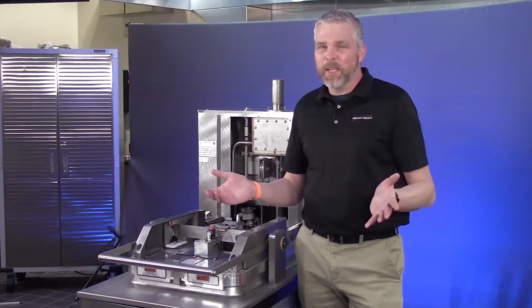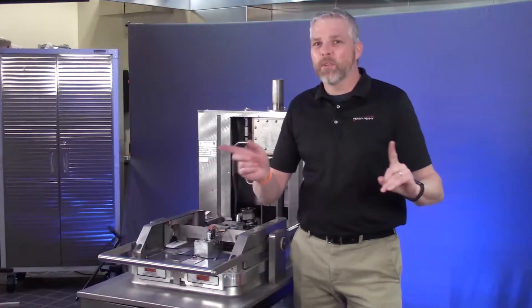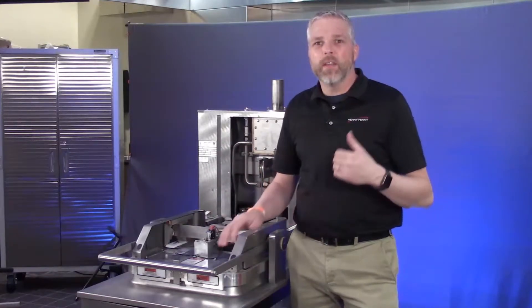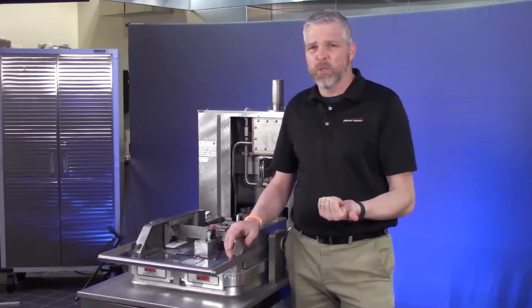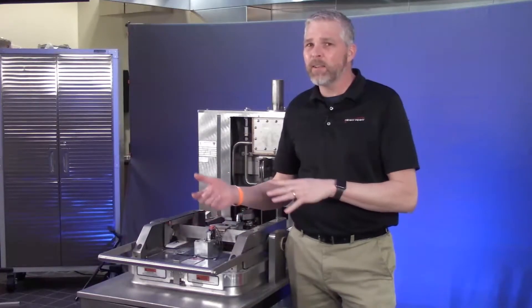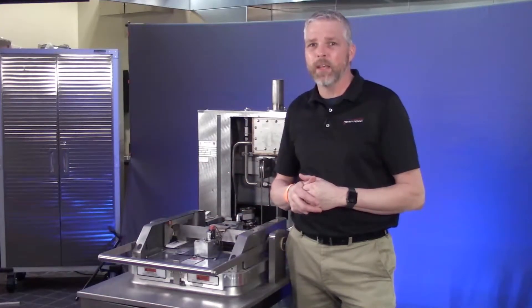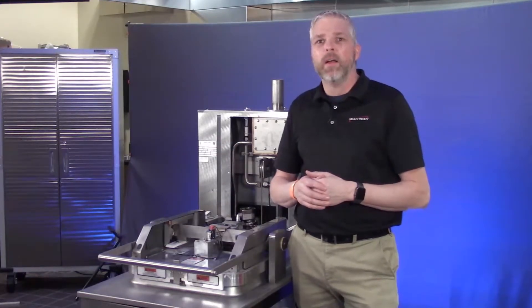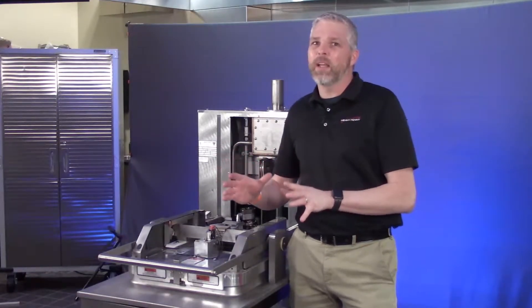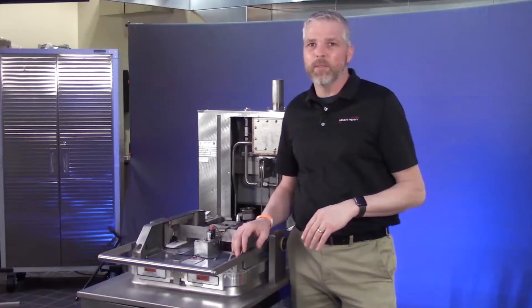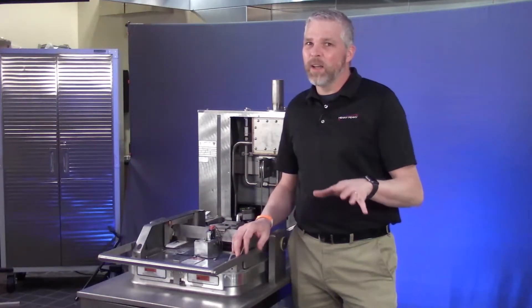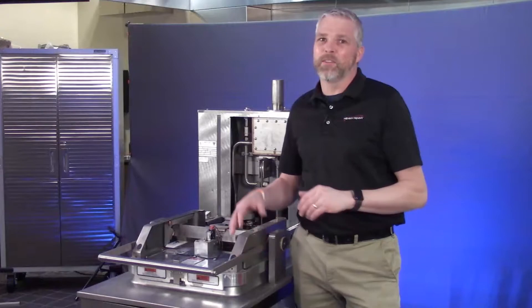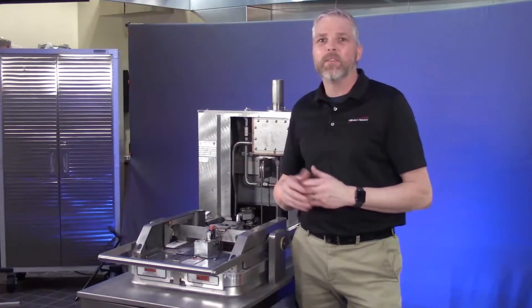So what does that mean? It means what you have to bring out to the service call on this one is a solenoid valve rebuild kit. You may or may not need that. A lot of times you can just clean the solenoid valve and take care of this, or clean the solenoid valve plumbing to take care of this. And you may want to, just to be on the safe side, grab an entire solenoid valve as well. That's very unlikely that you're going to need that, but just to make sure you get a good first time fix, take that one as well.